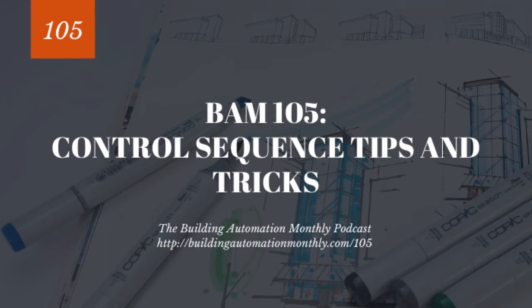However, think of another scenario like this, right? Chillers with isolation valves. I like to tell the story about how when I started off in this field, I didn't know you had to have the isolation valves open, and I went and tried to turn on a chiller with the isolation valves closed, and that did not work too well. But what if I were to just say, hey, chiller enable, and I put that in front of having the isolation valves on? That could work in some scenarios.